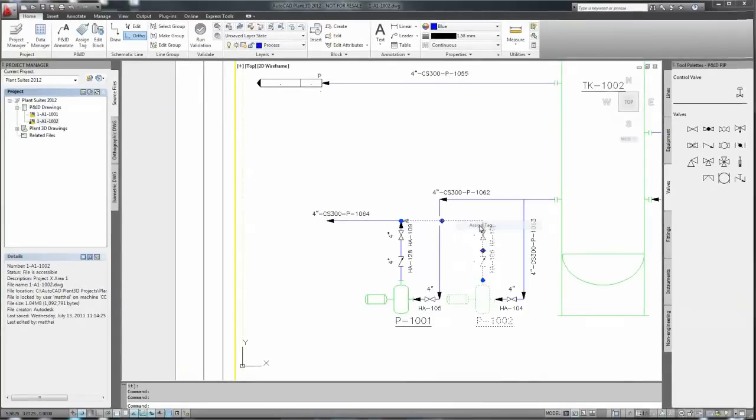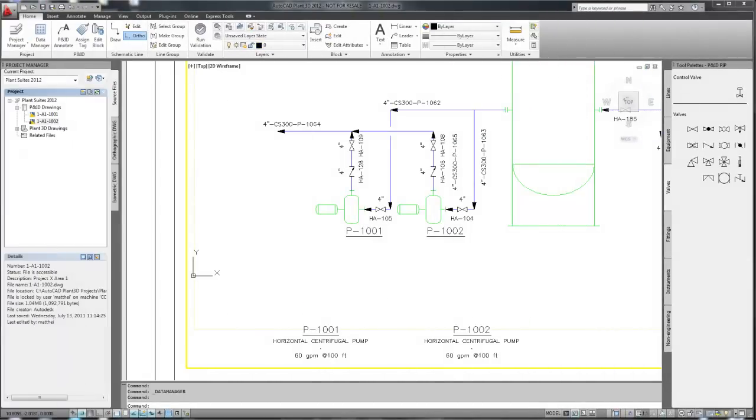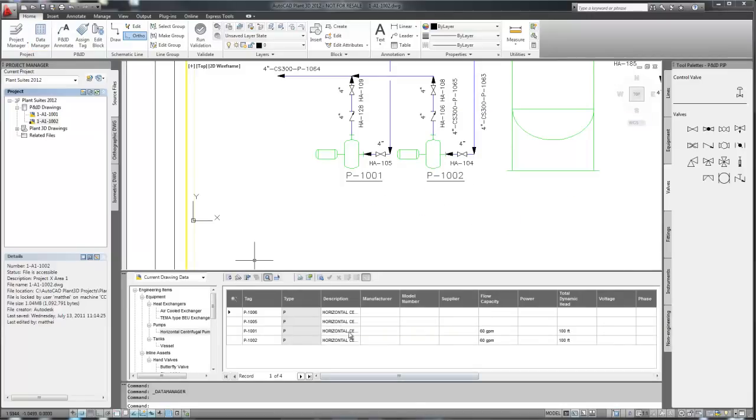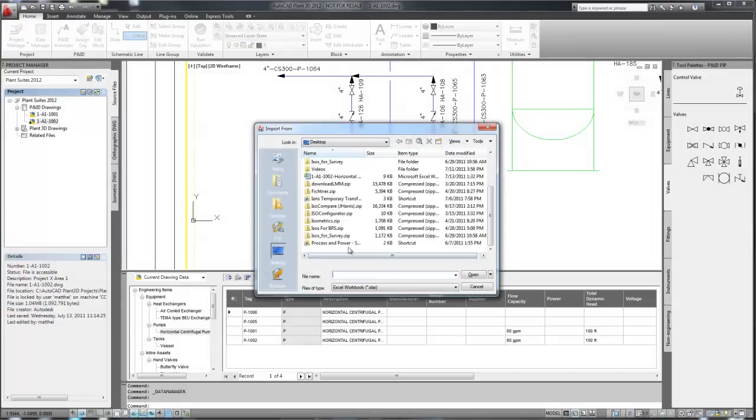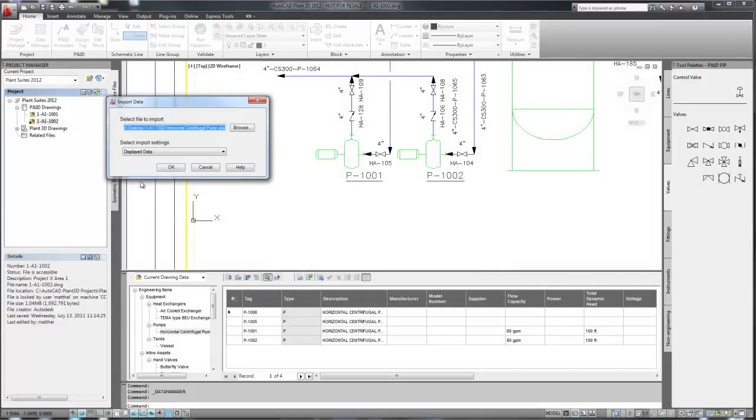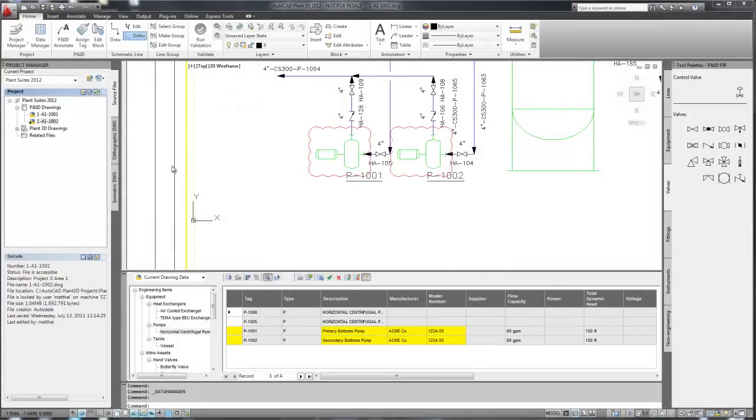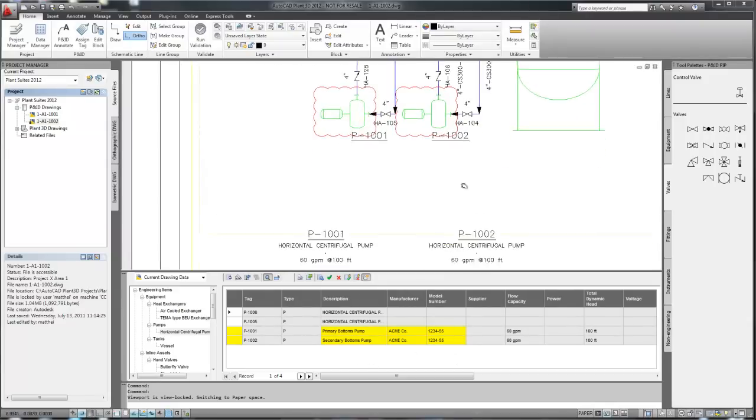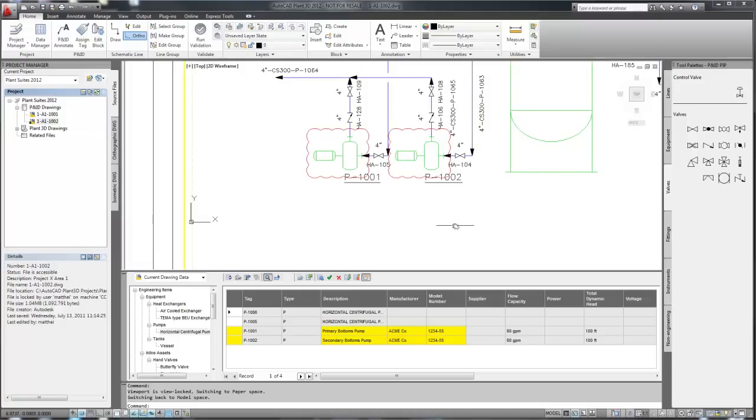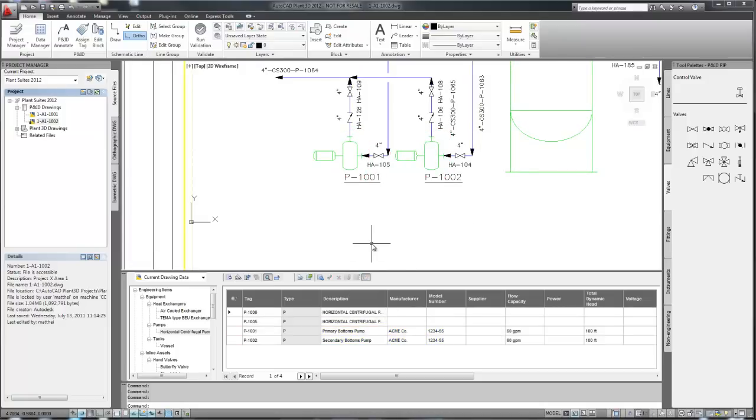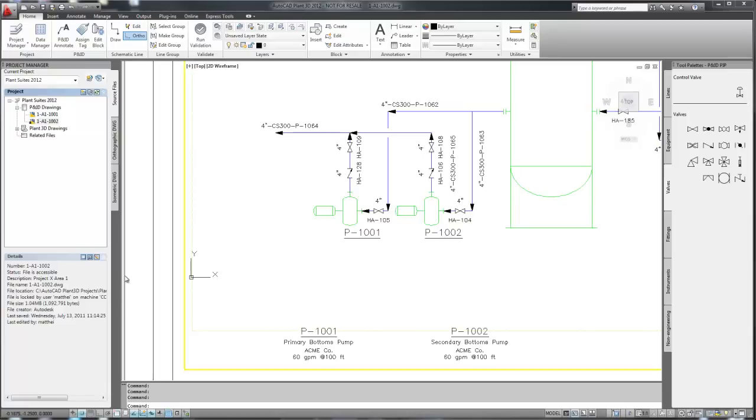Now one of the things that we often have to do is work with other engineers to provide information that needs to be shown on the P&ID. One way you can do this is through use of Excel spreadsheets. In this case, our pump data has come from spec sheets which have been entered into Excel spreadsheets. We import the data and the changes that have been made to the P&ID are shown. We can then determine whether these are acceptable. Once we accept them, all the data is updated, and as you see here, so are the tags.